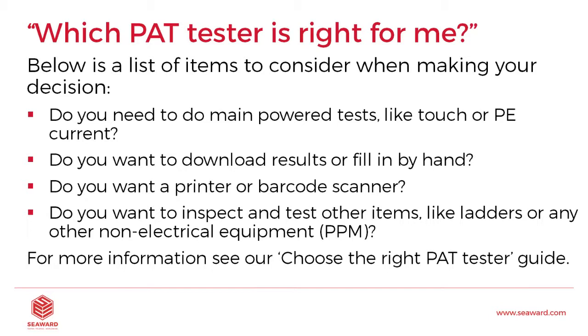The other bit then you've got there is, do you want to inspect and test other items like ladders or any other non-electrical equipment, PPM? The facility that we have in the Apollo 500 and 600s is that you can log and configure any test programs that you want. So if you are doing tick sheets for ladders or writing down Legionella temperature checks or anything like that, these can be set up in the PAT tester, asset ID downloaded, results kept, history, as an electrical appliance would do. So some really key points there to consider if you are looking at PAT testing.